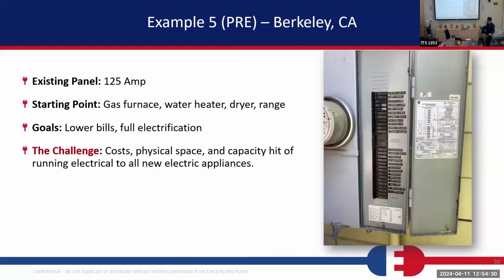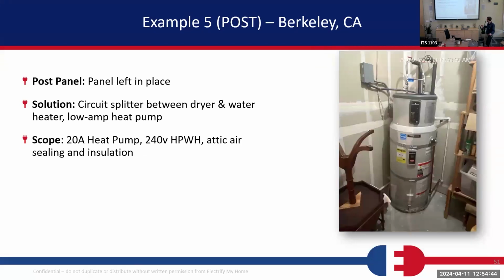Last one, or I might have one more. In Berkeley, 125 amp service, had a few breaker slots left, but to achieve his full electrification plan we needed a bit more space and capacity. So we did a circuit splitter between the water heater and the 20 amp heat pump, again specifying a 20 amp instead of a 25, 30, or 50 amp heat pump. In this case we were able to do that. We did a load calculation for the house to make sure we were meeting the right size, but we shopped around and looked for the system that would allow for the lowest breaker size.